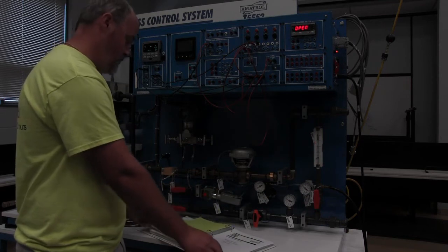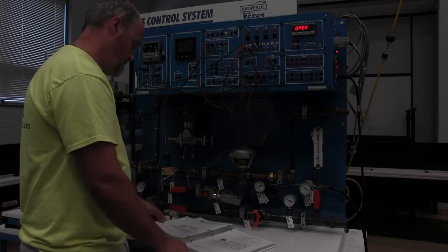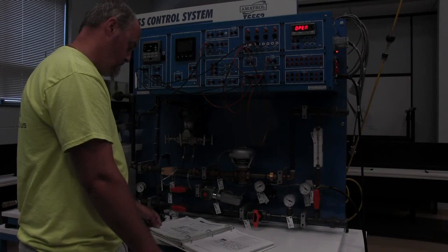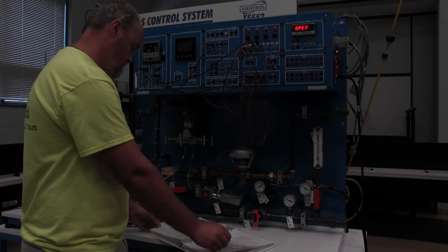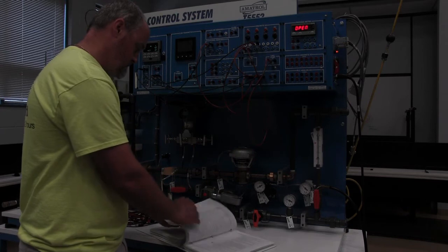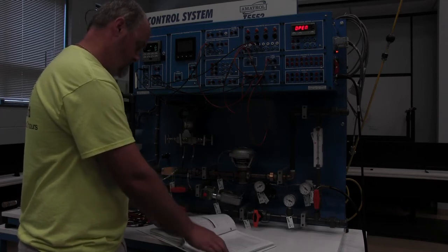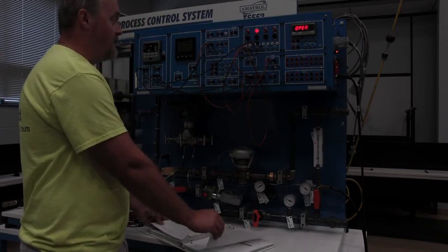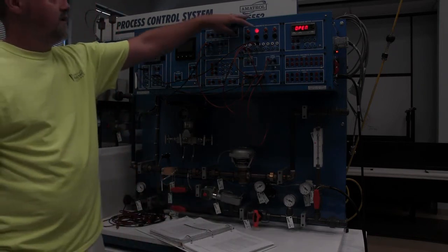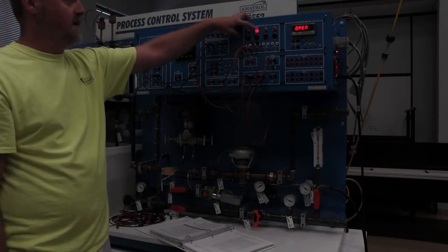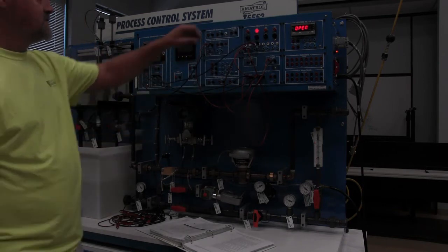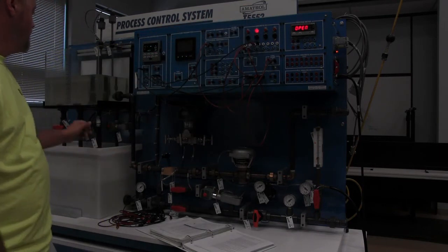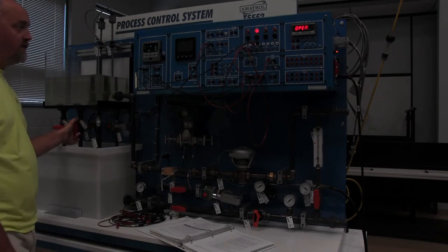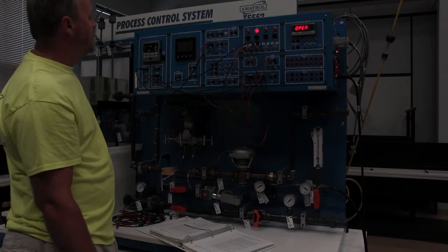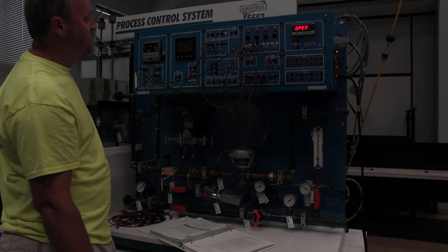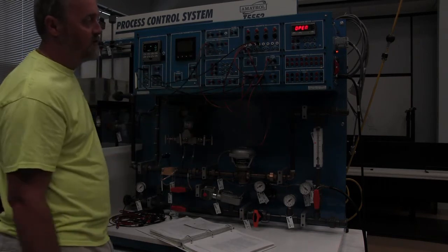We're at a 4.4 right now. We're at a 5. As we reach the 5, the alarm light came back on, indicating that we're now at a high level and we're in an alarm state. I'm going to turn the pump off and drain it back down below the 5. 5.4, 5.3, 5.2, 5.1, 5, and now we're back out of a high level.